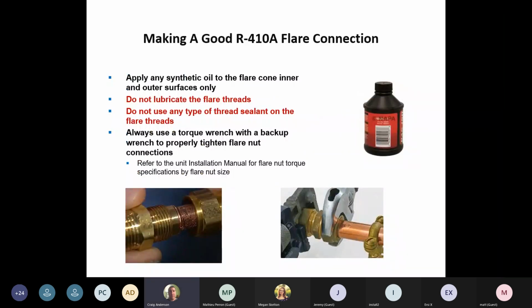So when we're doing a flare connection, in the manual, it'll actually tell you what the torque capacity is on that flare nut. Use a wrench on each side, so we're not twisting the copper and not changing that copper from round to oval. If we're changing it from round to oval or twisting it, then we're changing the inside diameter of that copper, which we don't want to do. So always use a backup wrench. If the flare nut's a little tight, take some synthetic oil and put it on the copper so that the flare nut will turn a little bit better. Do not put it on the flare fitting itself. If we're getting oil where the flare nut is connecting to the flare fitting, then we could get it loose a little bit. So make sure that's dry so we're getting a brass to brass connection. Once that's tight and it's torqued, it should not leak as long as we have a good flare.